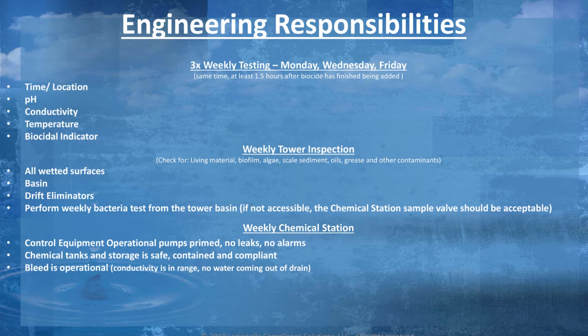Last, you should take a bacteria test from the basin of the cooling tower if possible. Remember, it takes 2 days to develop the results of your bacteria test. If the results are greater than or equal to 10,000 colonies, or about 50 individual dots on the agar plate, a corrective action must be performed. We highly recommend you call your water treatment company immediately.